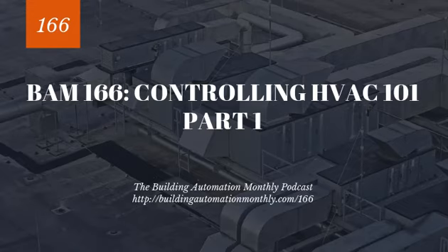Now, that's temperature control. But what about humidity? Humidity we tend to do by actually wringing out the air using a cooling coil to bring the air to saturation, drain out the water, and then heat the air back up a little bit, actually in the space. And we do that either through mixing a mass of air with an existing mass of air, or through reheating the air.